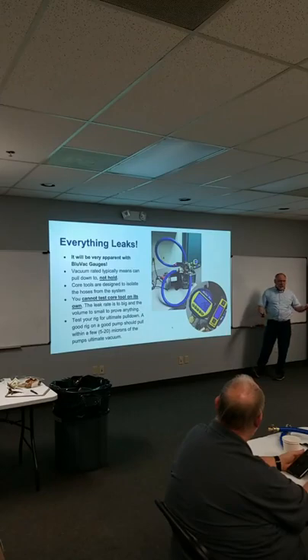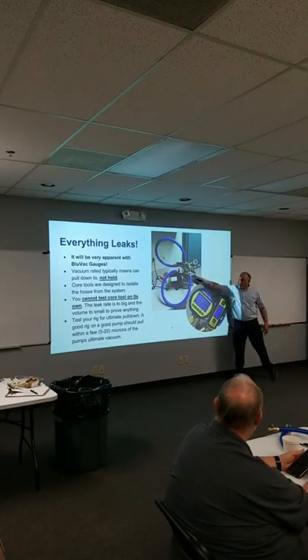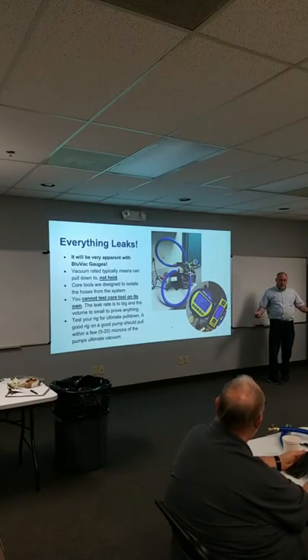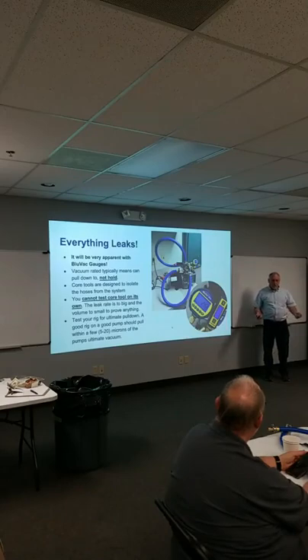We run them down at trade shows all the time. Once we get the hoses dried out, we can pull these down all day. We pull down south of 10 microns. But you can't close that valve on the side here. This valve is not a vacuum rated valve. It's a blank off valve. It's not meant to hold vacuum, never was.